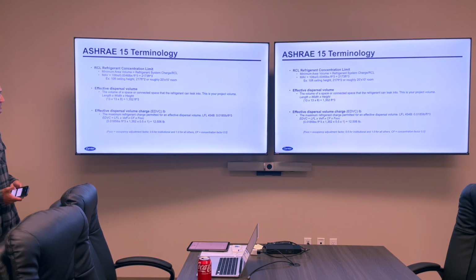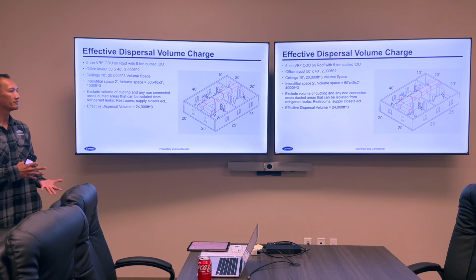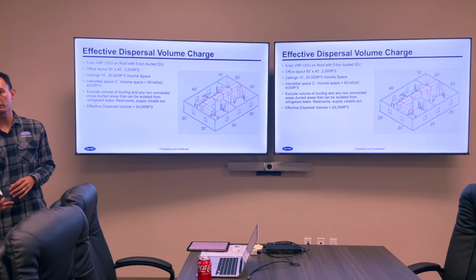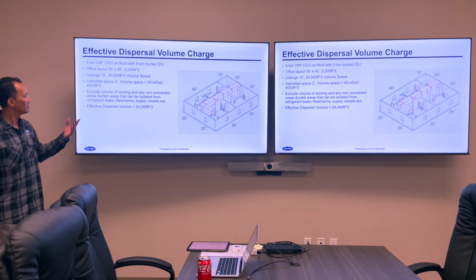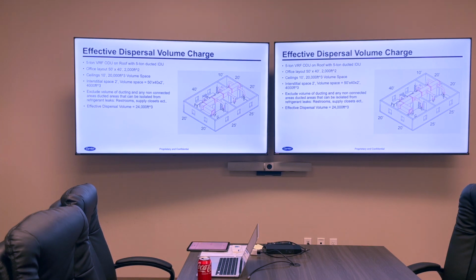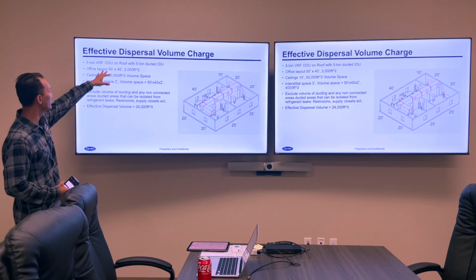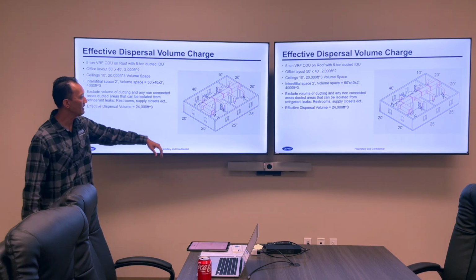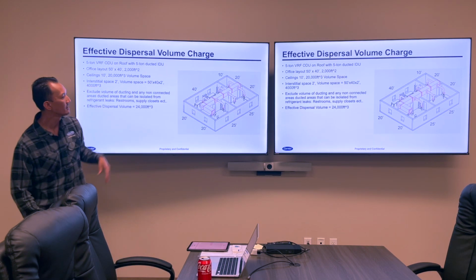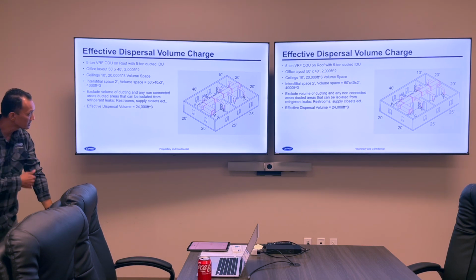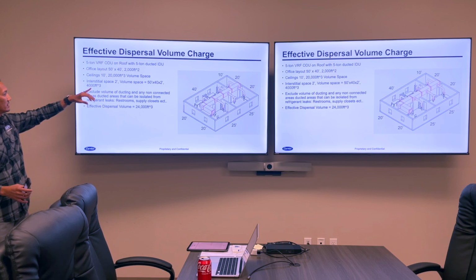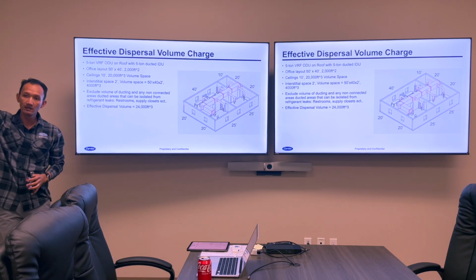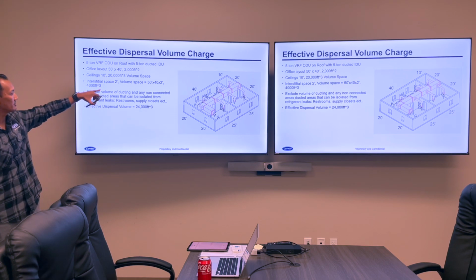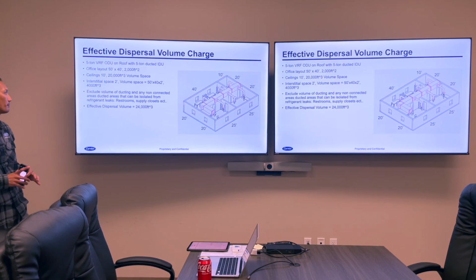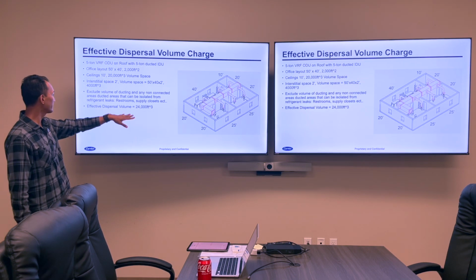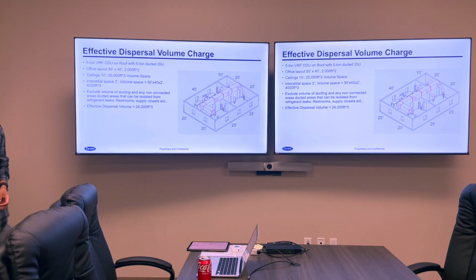So let's look at an example system. We have a simple office building with different rooms, footprint of about 2,000 square feet, 40 feet by 50 feet. We're assuming 10-foot ceilings. And we're using a 5-ton VRF outdoor unit with a 5-ton ducted indoor unit that is installed above the ceiling space. And since we are using open return, we can actually include that interstitial space above the ceiling, so about 2 feet in this example. So our total height would be 12 feet. If you do the math, you get an effective dispersal volume of 24,000 cubic feet for this example.